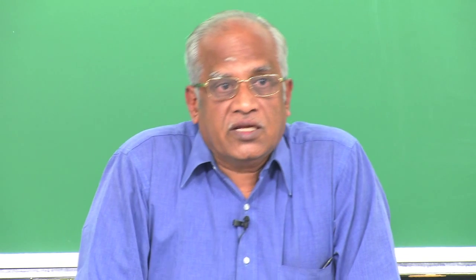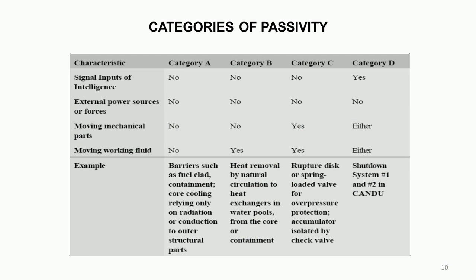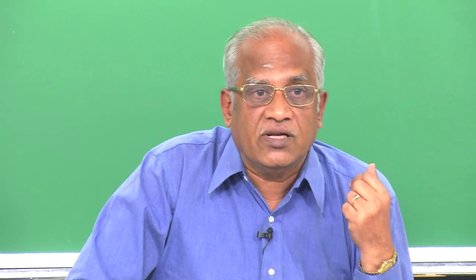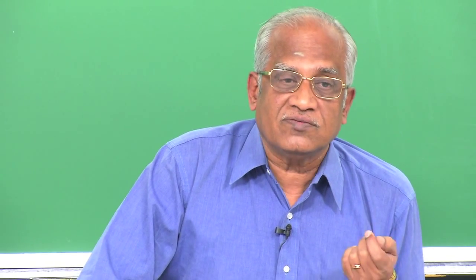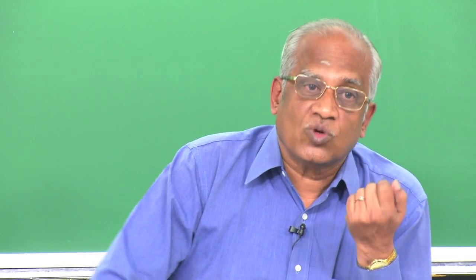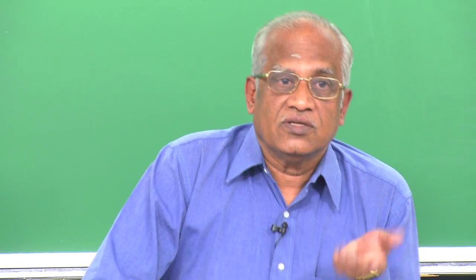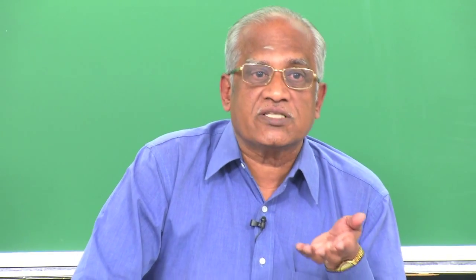In Category C there is a moving working fluid and also moving mechanical parts. Examples include a spring-loaded safety valve, a rupture disc for overpressure protection, an accumulator, or a gravity tank kept at a very high level with a check valve. The check valve involves mechanical movement — that is another type of degree of passivity, Category C.